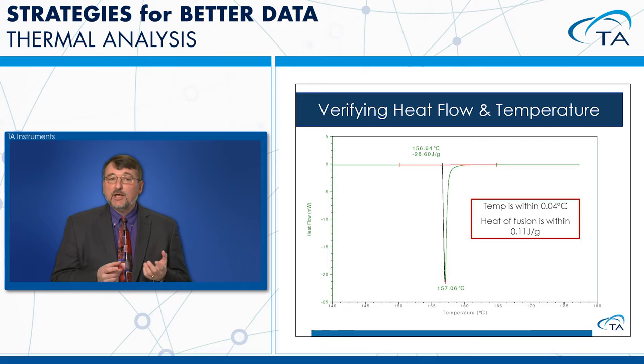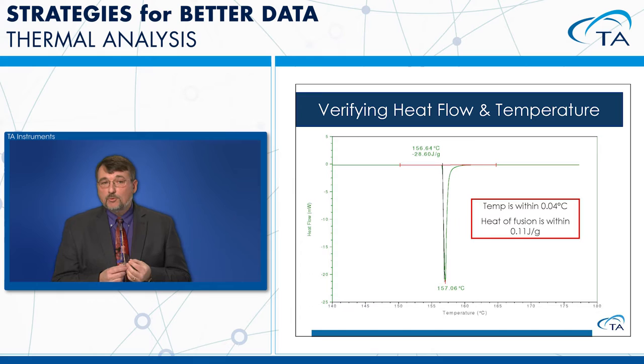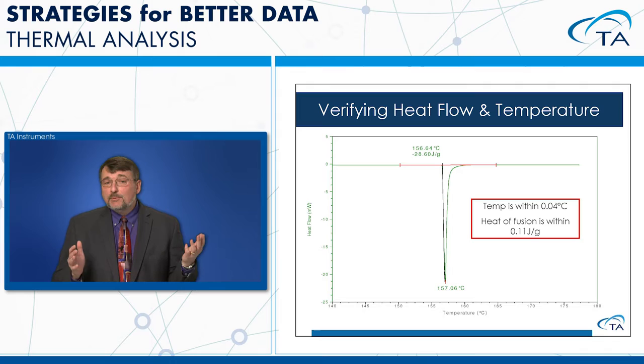This slide shows a verification of a DSC cell by running indium, plotting heat flow versus temperature and looking at the melt. The onset of that melt is 156.64 degrees — only 0.04°C away from the true melting point of indium. The heat of fusion is only 0.11 J/g away from the true value. That's excellent performance; I'm ready to run samples without recalibrating.